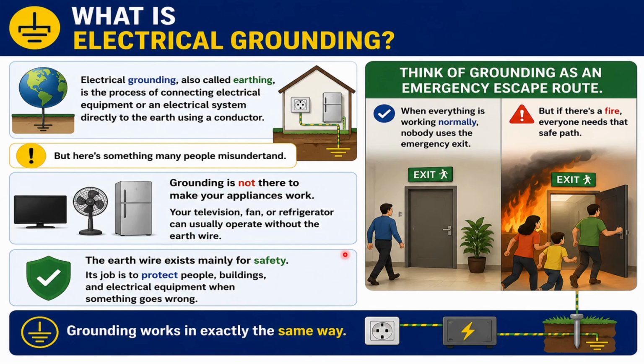So think of grounding as an emergency escape route. When everything is working normally, nobody uses it. For example, like an emergency exit, right? When everything is working normally, nobody uses it. But when there's a fire or an emergency, then it is used. So just use the example of an emergency exit. When everything is working well, there's no need for you to use that. But when an emergency arrives, that's when it becomes very, very important. So grounding works in the exact same way. All our appliances are connected to earth. If everything is working properly, there's no need for it. But when we have an earth leakage or a failure of insulation and all of that, that is when the earth conductor comes into play.